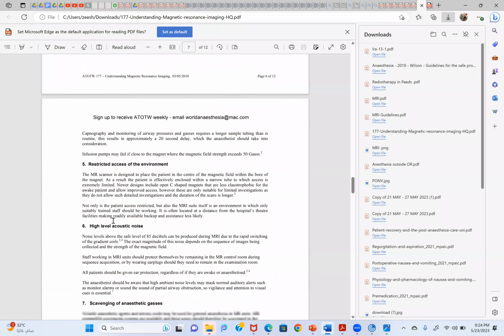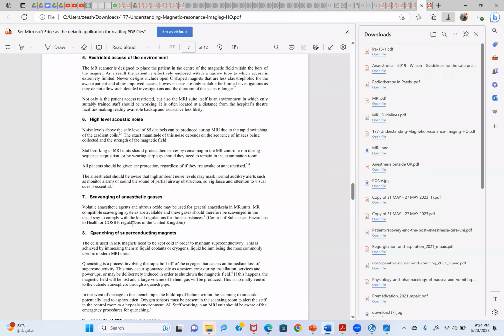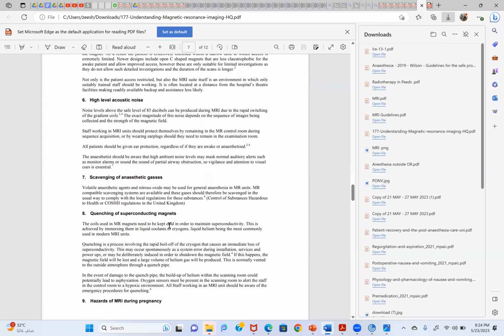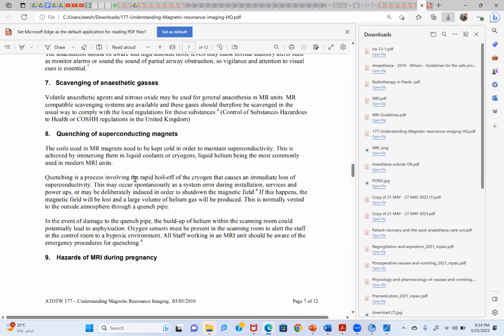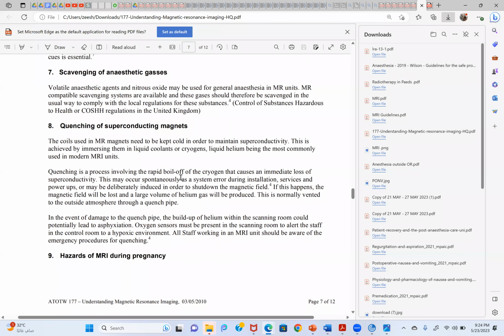Okay. So restricted a high level of scavenging of anesthetic gases. Usually it's not there. Okay. And what else? Quenching. So we can have some words about quenching. Quenching is a process involving the rapid boil-off of the cryogen that causes an immediate loss of superconductivity. This may occur spontaneously as a system error during installation, services, or power-ups, or may be deliberately induced in order to shut down the magnetic field. If this happens, the magnet will be lost and a large volume of helium gas will be produced. This is normally vented to the atmosphere through a quench pipe, but still you should be knowing about it. In the event of damage to the quench pipe, the buildup of helium within the scanning room could potentially lead to asphyxiation. Nothing will be happening to the patient, but the staff will be asphyxiated.